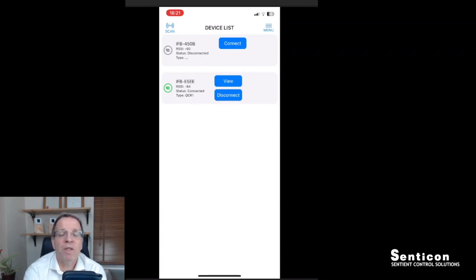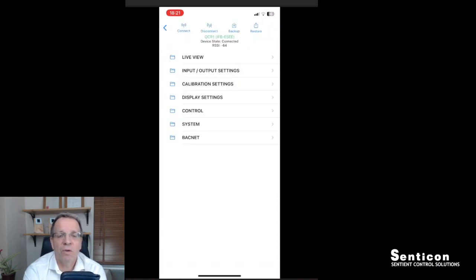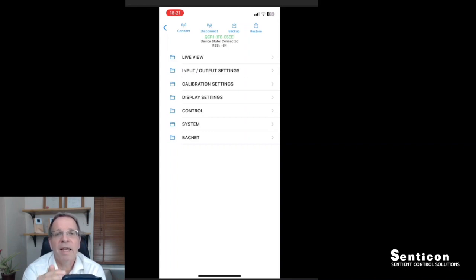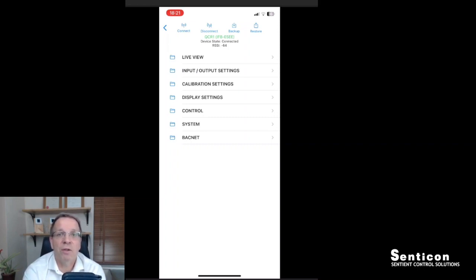It identifies the device name or device type as QCR1 — a quality CO2 controller. I click the view button and it takes you to the configuration menu, where at the top you can see the Bluetooth connect/disconnect buttons and the backup/restore function. Backup and restore allow you to configure one device, back it up on your phone, and then restore it to another device of the same model. When you have multiple rooms, it's very easy to copy and paste the configuration from one room to another.